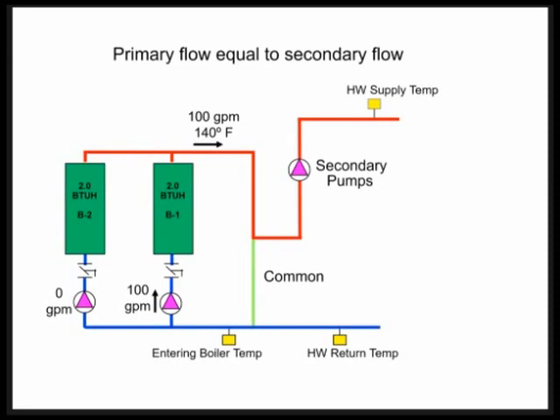100 GPM in my secondary loop, going out at 140 degrees, and I have no flow in the common pipe. Because I have 100 GPM going out into my secondary loop, I also have 100 GPM coming back. And because in this scenario we're perfectly loaded, which rarely happens, we have a 100 degree return water temperature coming back. That means my entering boiler temp is also 100 degrees because I have 100 GPM going into my boiler.